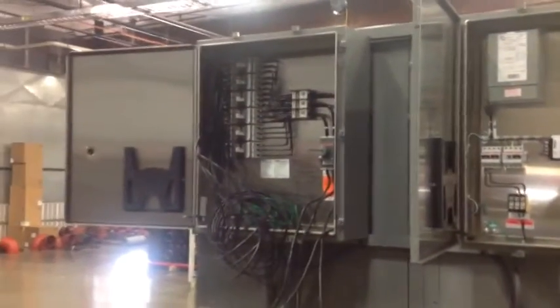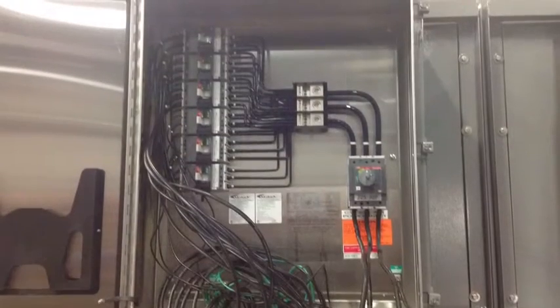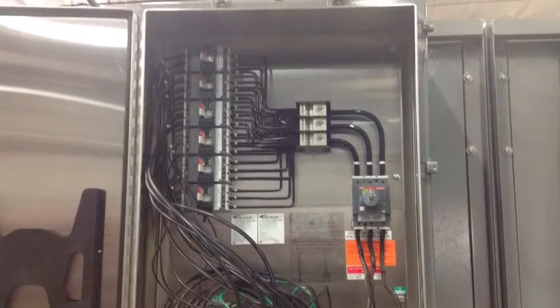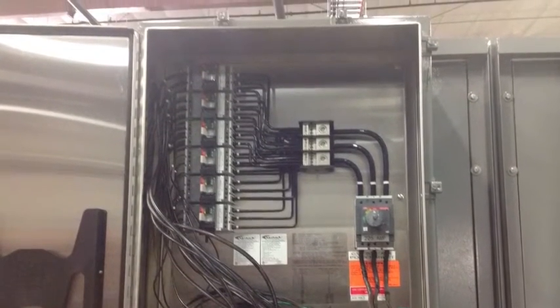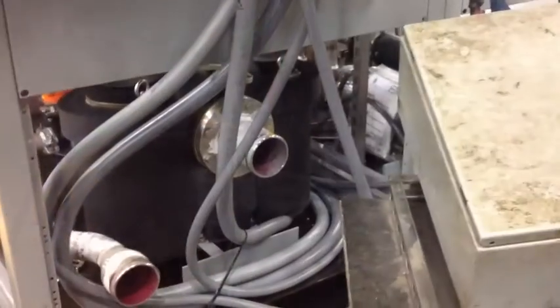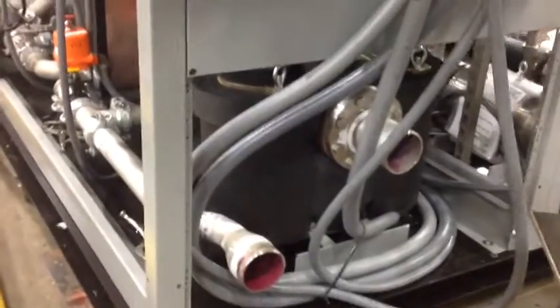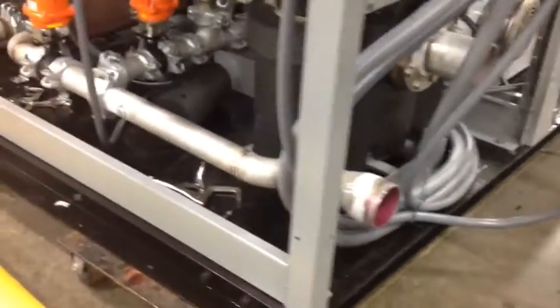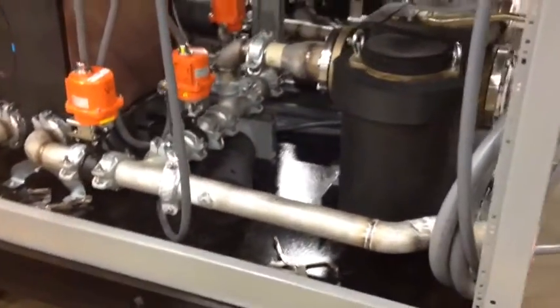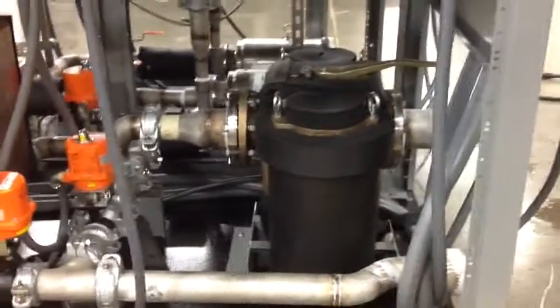Moving left, we see the single point power junction box. This is the single point that distributes power to all of the mechanical modules, the pump module, and the heat exchanger controls. This is the entering connection through a dual basket strainer from the comfort cooling loop, as well as the piping connection that runs back to the comfort cooling loop.